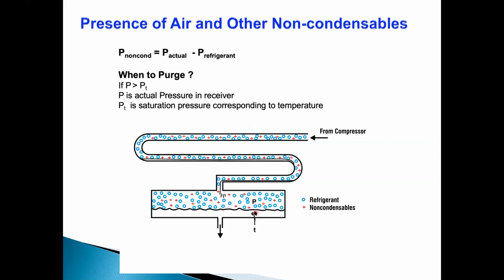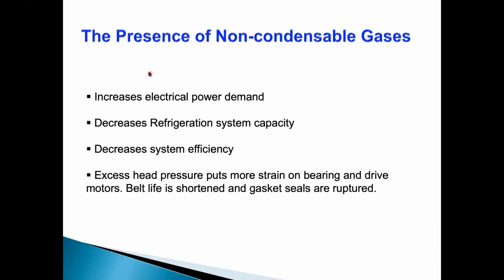You measure the temperature of the liquid in the receiver and convert it into the saturated pressure corresponding to this temperature. The pressure difference is your air. So what is to be done with this air? Air has to be removed immediately because air does not condense or evaporate in the refrigerant system. So what happens is it remains like a free passenger traveling on a train.